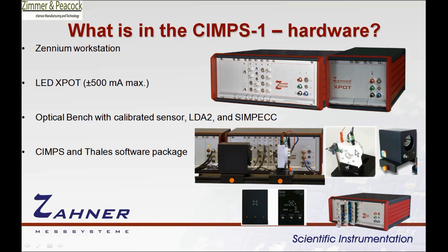The PEC2 cell is also an option you'll need to include. On the hardware front, you also have the SIMPECC, which is a dummy cell containing four diodes and discrete electrical components. It allows you to calibrate, check, and test to make sure everything is working fine without actually having to have a photoelectrochemical experiment running.